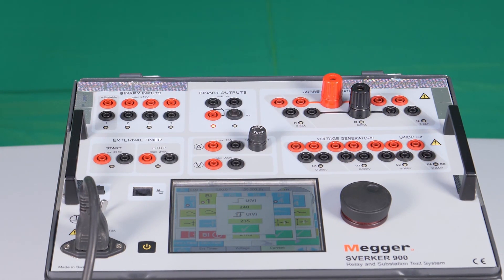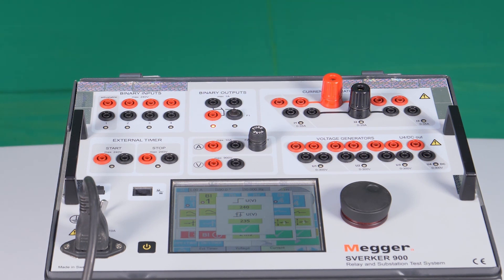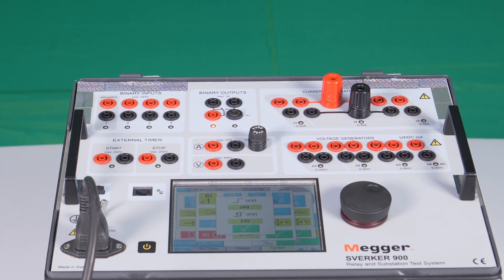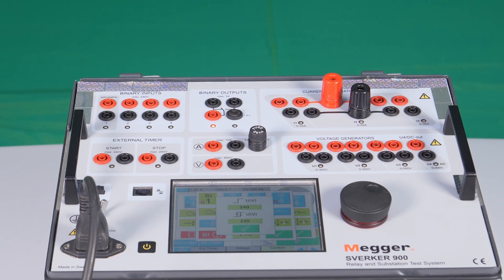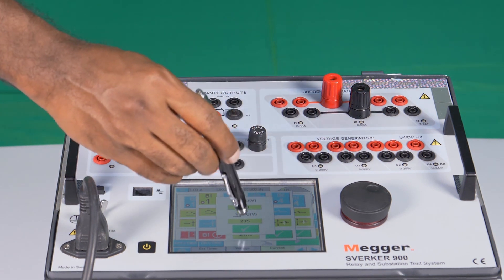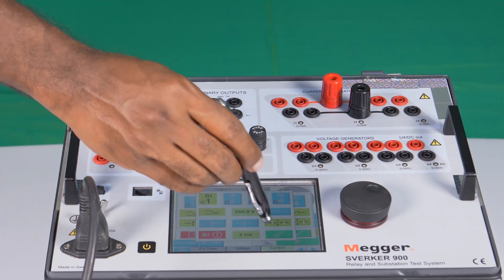The drop-off value called as hysteresis can also be configured which normally varies from 2 volt to the pickup minus 3 volt. Example, if the pickup is set to 100, then the hysteresis can be set to 2 volt to 97 volt. If the pickup is set to 200 volt, then the hysteresis can be set from 2 volt to 197 volt.